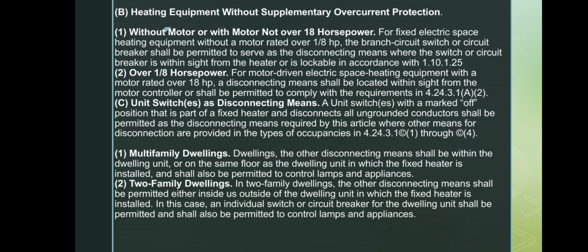Next slide discusses heaters without supplementary overcurrent protection. First, without motor or motor not over 1/8 horsepower. The branch circuit breaker or switch may act as the disconnecting means as long as it is within sight or lockable. Motor over 1/8 horsepower. A disconnect must be within sight of the motor controller, or it must meet the same rules listed in 4.24.3.1(A)(2).